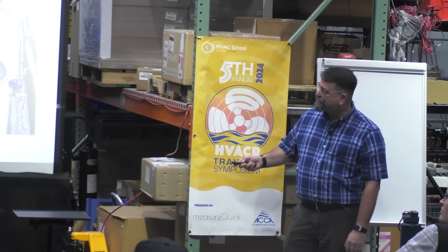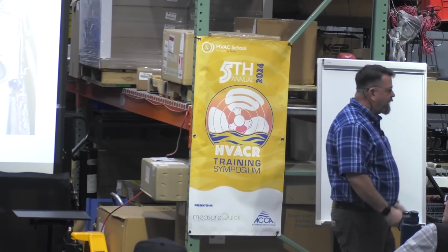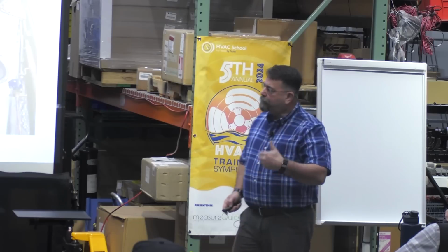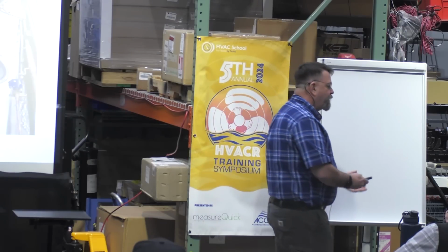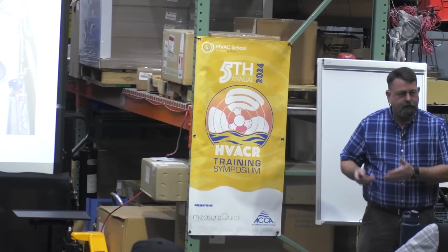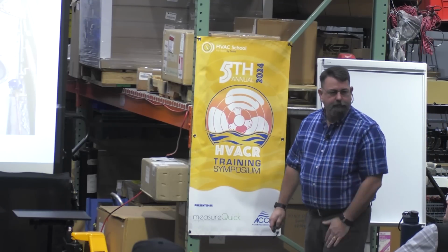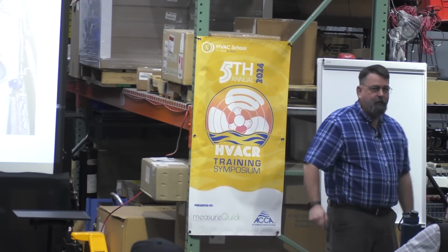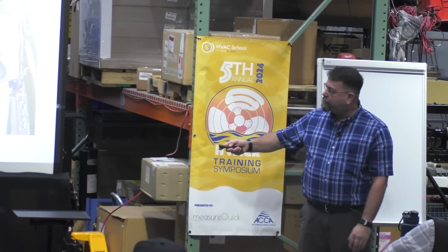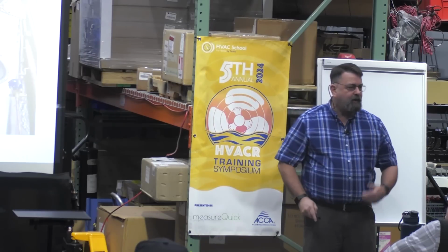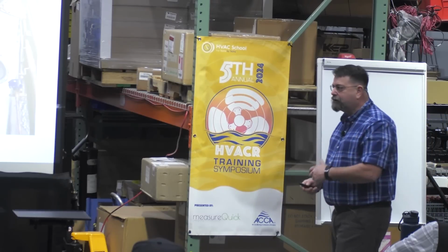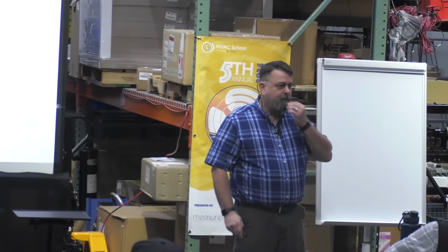It's going to suck it in. What's it sucking in? Sales floor air, right? Yeah, we have that exact same, and it's just different, right? It's a checklist you're going to go through, each one of these items. The cause is different, but the result is because of the same problems, right? Leaks in my air system, leaks in my return, short cycling air. Instead of losing it into the attic, I'm just recirculating it, right? Those kind of things. Plenum being tight, sealed, yeah, it's the same stuff. It just looks different. All right, yeah, go ahead.